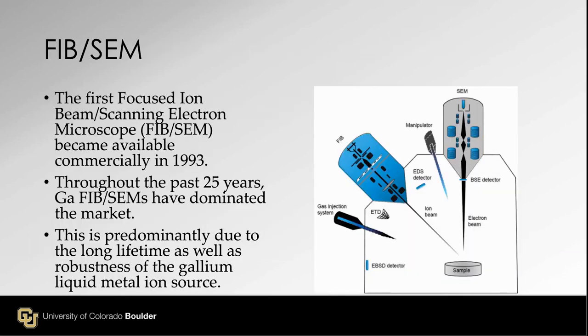Finally we are here: FIBSEM. The first focused ion beam scanning electron microscope instrument became available commercially in 1993. It has two columns: one is the SEM column, typically top down, straight down, and the FIB ion source is connected sideways.